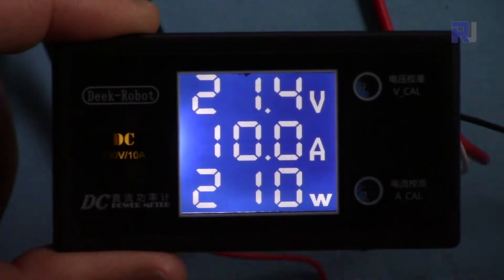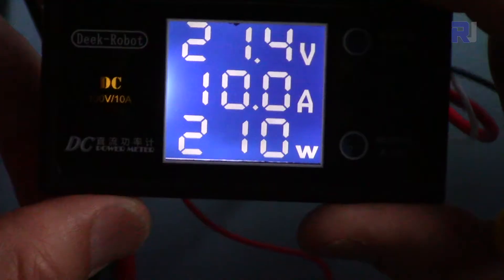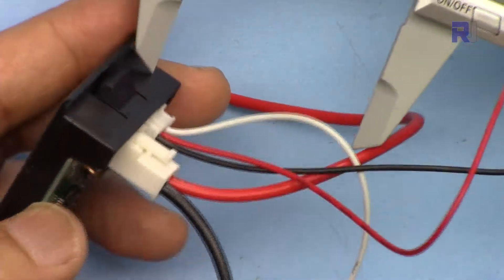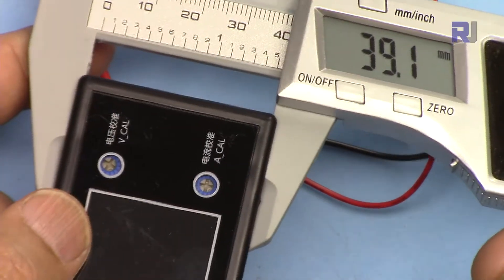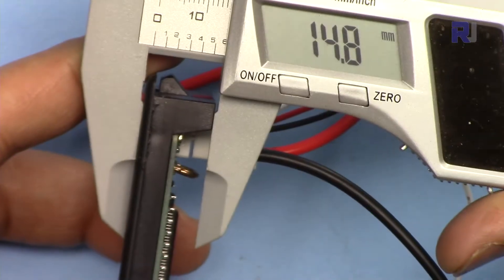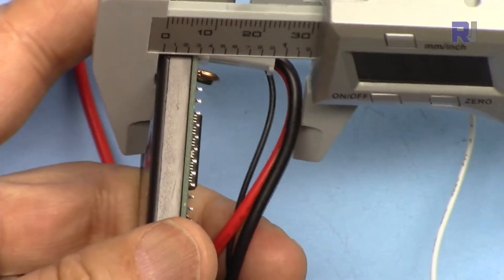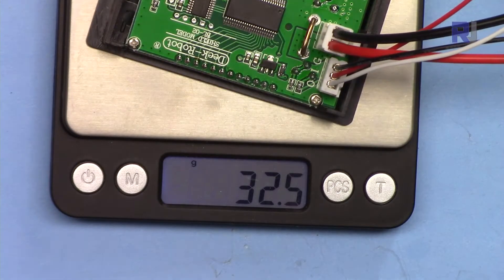We have simple connections here — three wires for the voltage, two wires for the current. With the light now off, this is how you will see it. There is also some backlight and it can be viewed very easily — it's very bright. The length of this is 79.3 millimeters, the width is 42.8 millimeters. If you want to create a hole on the panel and insert it, that size is 39.1 millimeters wide and 71.4 millimeters long. The depth of the module is 14.8 millimeters with the connector. It weighs 32.5 grams.